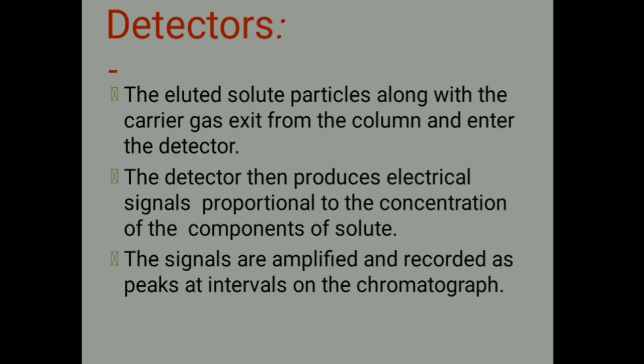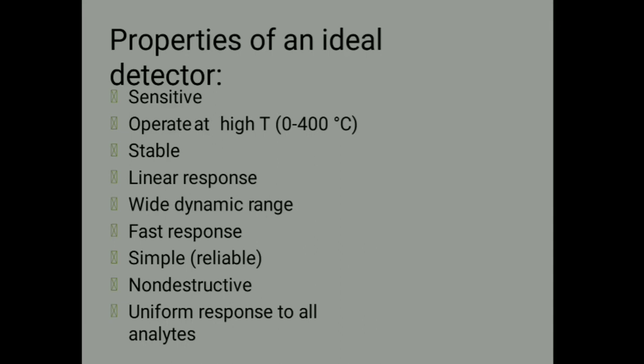Next we have detectors. The eluted solute particles along with the carrier gas exit the column and enter the detector. The detector then produces an electrical signal proportional to the concentration of the components of the solute. The signals are amplified and recorded as peaks at intervals on the chromatogram. Properties of an ideal detector: sensitive, able to operate at temperatures around 0 to 400 degrees Celsius, stable and reproducible, linear response, wide dynamic range, fast response, simple and reliable, non-destructive, and uniform response to all analytes.